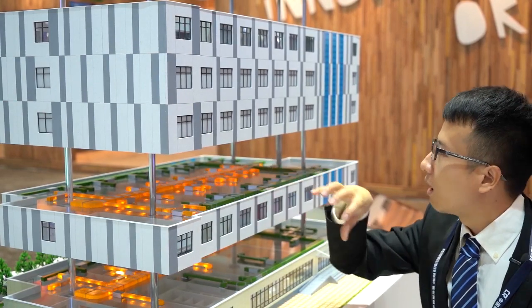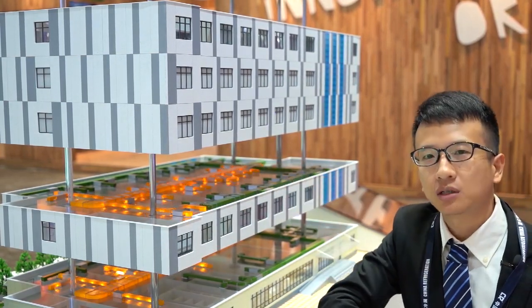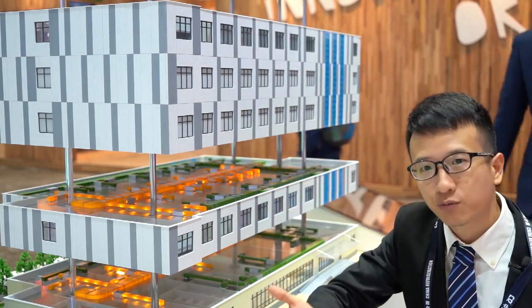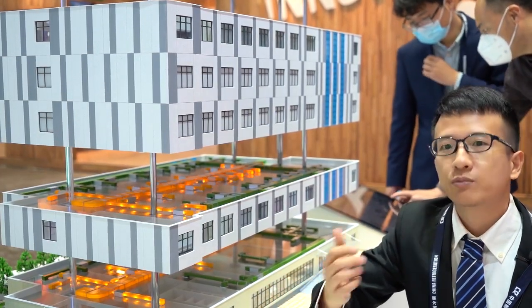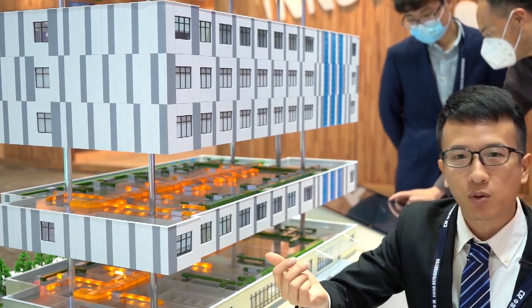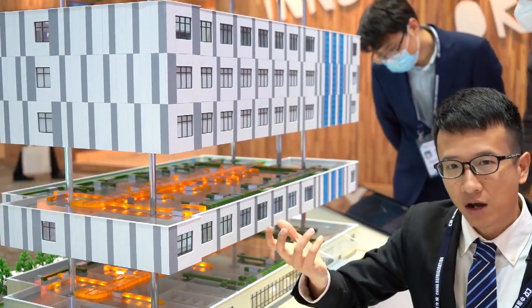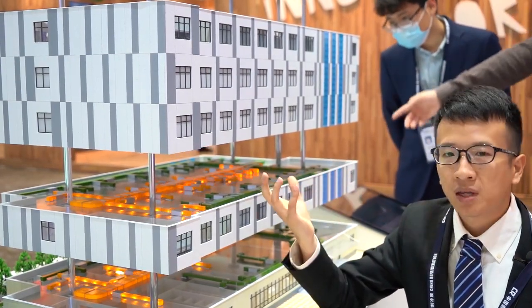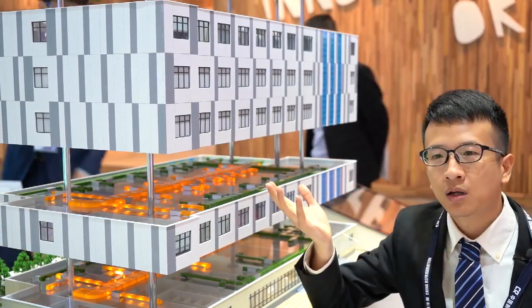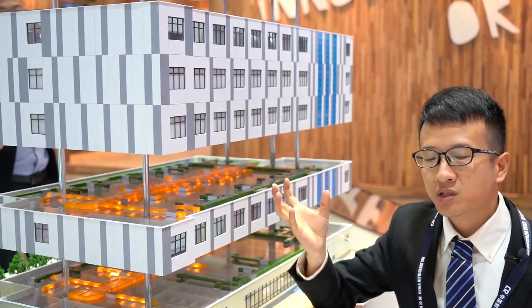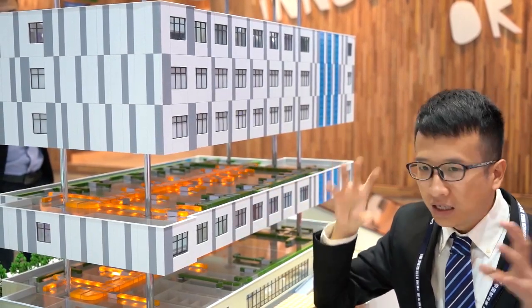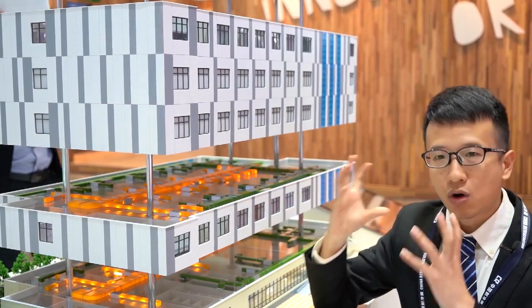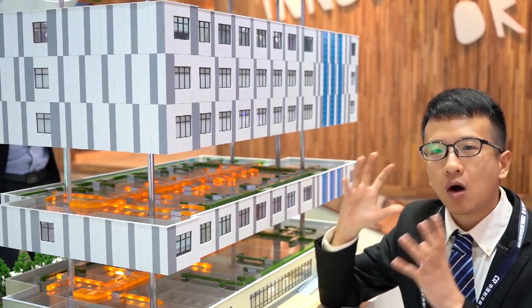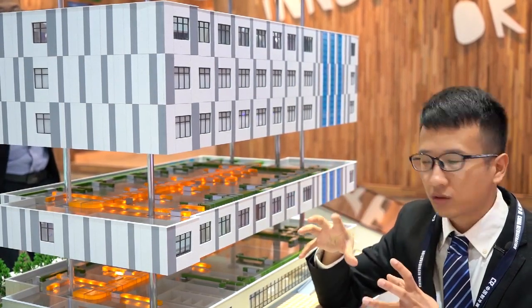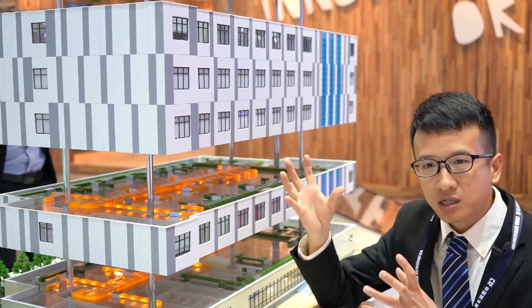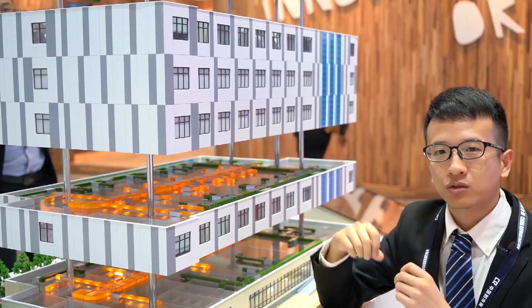So the air ductings cover all the rooms here, but as we introduced before, some rooms are usually positive pressure, such as the reception hall, administrative department, or inpatient department. Those departments usually have a positive air pressure. And for some other rooms where there is air contamination, such as the operation room or contaminated room, the air pressure should be negative, which means in those rooms, the air should not cross flow with other rooms and should not flow outside the rooms. If the air in the negative pressure room goes out, the air would contaminate other rooms, which is dangerous.